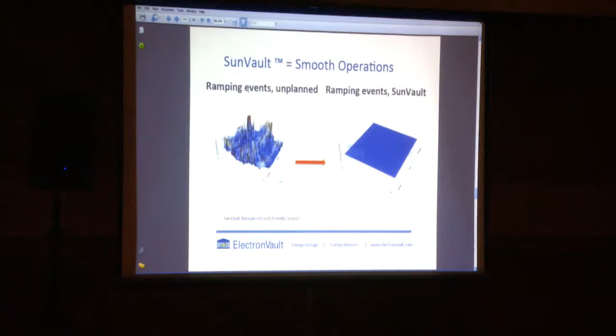So it's smooth the curve, but more importantly than smoothing, it's control the ramp rates so that you're not moving faster than the other things that are on the generation mix. That way there's other things that can fill in for you when you ramp down. And you can ramp up in a way that's graceful in allowing other things to ramp down. With the typical SunVault 1000 type installation on the DC side, we can completely eliminate unplanned ramping events for any site in California or in Baja.